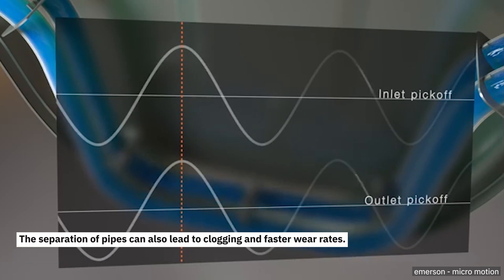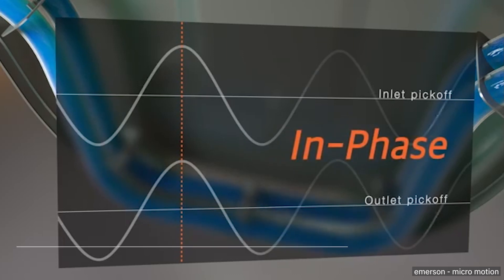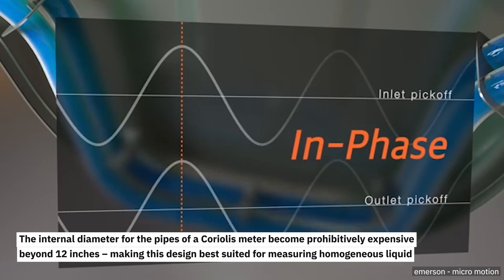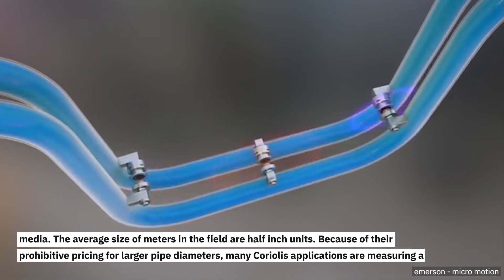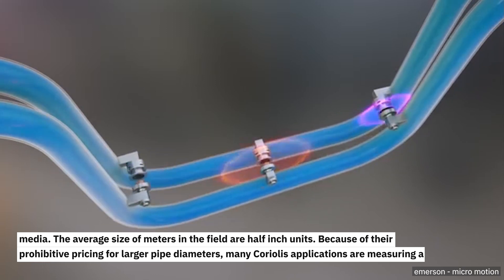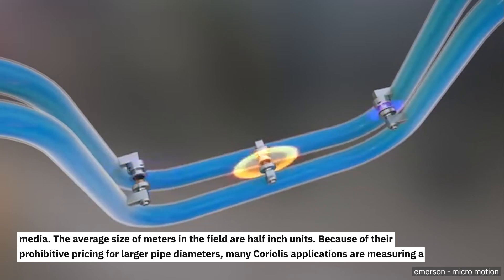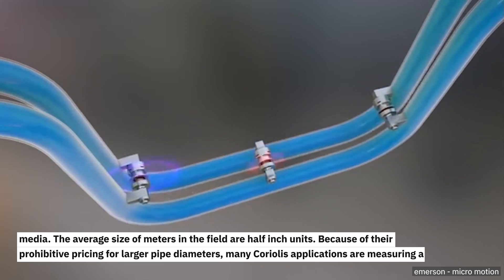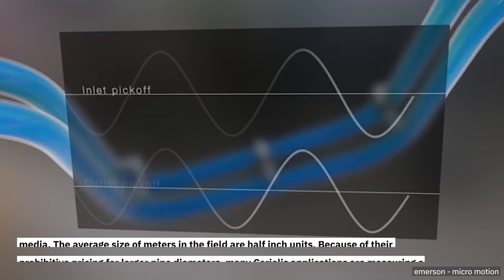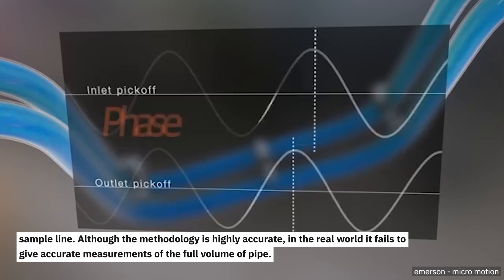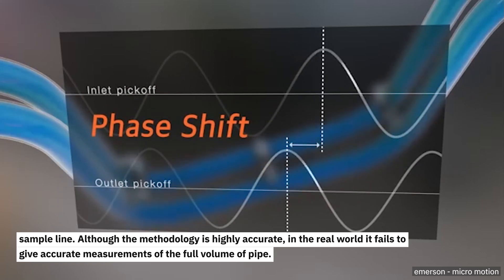The separation of pipes can also lead to clogging and faster wear rates. The internal diameter for the pipes of a Coriolis meter becomes prohibitively expensive beyond 12 inches, making this design best suited for measuring homogeneous liquid media. The average size of meters in the field are half-inch units because of their prohibitive pricing for larger pipe diameters. Many Coriolis applications are measuring a sample line. Although the methodology is highly accurate, in the real world it fails to give accurate measurements of a full volume of pipe.